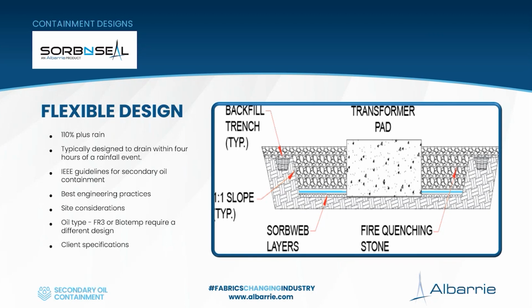We're using chemistry with the polymer, so we need to make sure the polymer in the fabric is compatible with the oil in the transformer. We've tested a multitude of mineral oils, so we're confident we can address most mineral oils on the market. Every once in a while we come across one we haven't seen before—if that happens, we send you a test kit you can do yourself, a 60-second test that doesn't cost anything, with instructions included. It's like a little home science project, very easy to do. But otherwise, we've encountered pretty much any type of mineral oil out there in the market.